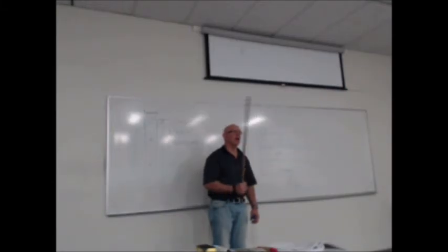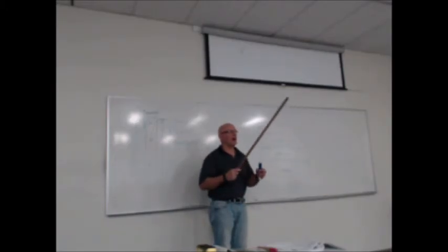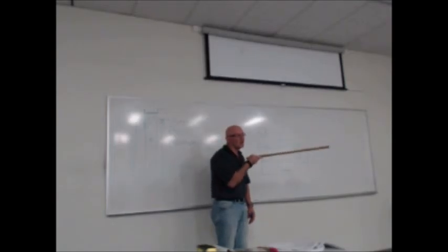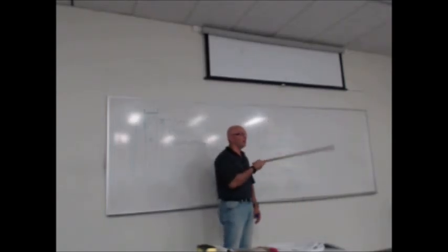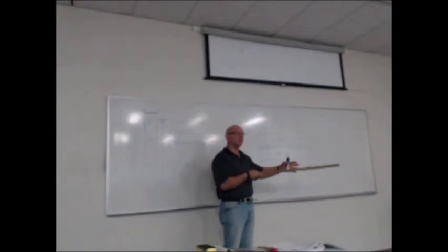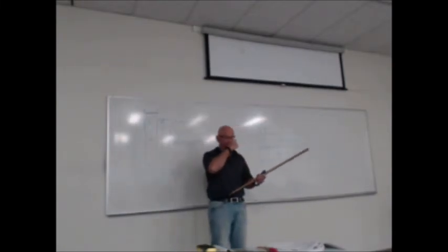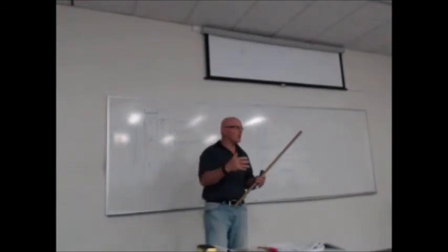Where do you put your thermostat? Above the return air. So if we put our return air central next to a heating duct, isn't it going to get a false reading? You can't be near a duct. That's right. So you want it in the coldest area of the house, so that the coldest area of the house is at least going to be the temperature. That's what we're thinking about, right? So you've got to think about where you're putting your return air.